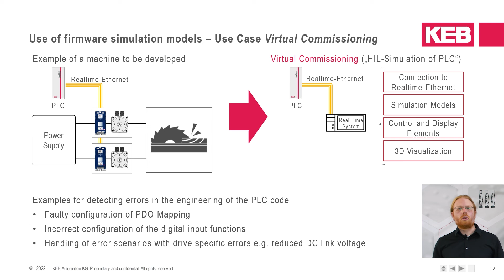With this setup, tests of first functionalities are done virtually before the real commissioning. Some possible examples to detect errors in the PLC code are faulty configurations of the PDO mapping, incorrect configuration of the digital input functions, and also handling of error scenarios with drive-specific errors. For example, we assume a reduced DC link voltage and the PLC code has to ramp down the system.